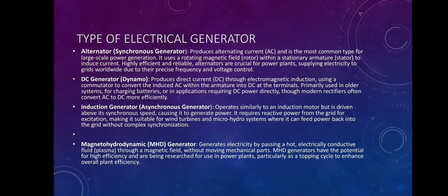Induction generator, an asynchronous generator, operates similar to an induction motor, but is driven above its synchronous speed, causing it to generate power. It requires reactive power from the grid for excitation, making it suitable for wind turbines and microhydro systems, where it can feed power back into the grid without complex synchronization.